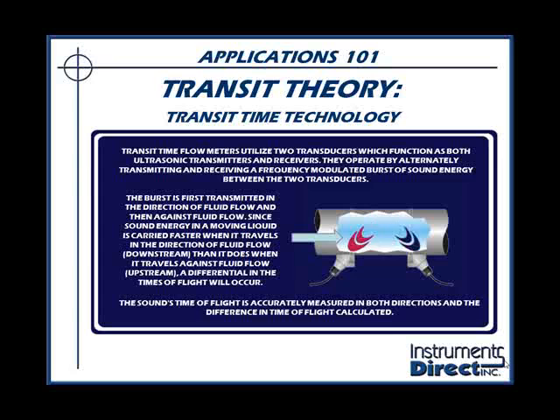The electronics will take note of how long it took to transmit from the first transducer to the second transducer. Well, the second transducer downstream to the right-hand side will at the same time send a burst of sound across the pipe, reflect off the back wall to the first transducer, and the flow meter will take note of the time it took to transmit from the second transducer to the first transducer. Now, both of the signals are influenced by the arrow on the left, which is the current of the liquid. So in this case, the faster the current, the longer it takes from the transducer downstream to get to the transducer on the upstream side.